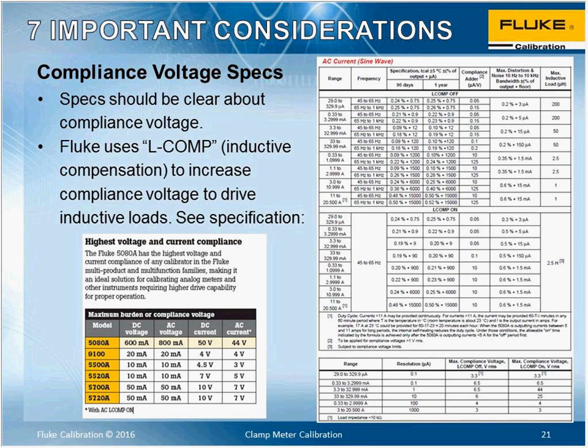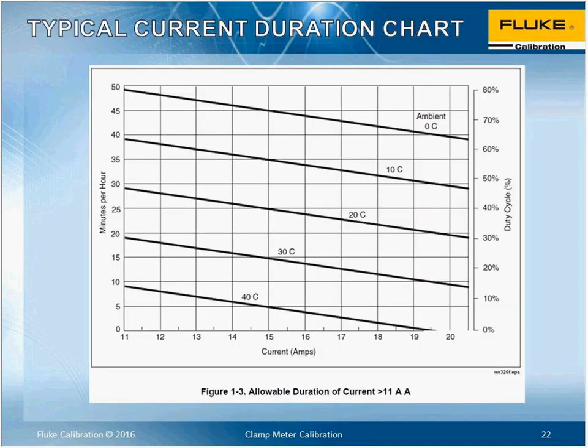On our spec here, you can see there's a section of the A side where it says L-comp off, and then there's a section called L-comp on. And there are differences between the accuracies. But one of the things that we've done with our products is to evaluate the load of all of the Fluke industrial group clamp meters and such, all the ones typically on the market, to make sure that we've got enough accuracy for those with the L-comp on. So that's something to consider when you're looking at the current functionality of the product.